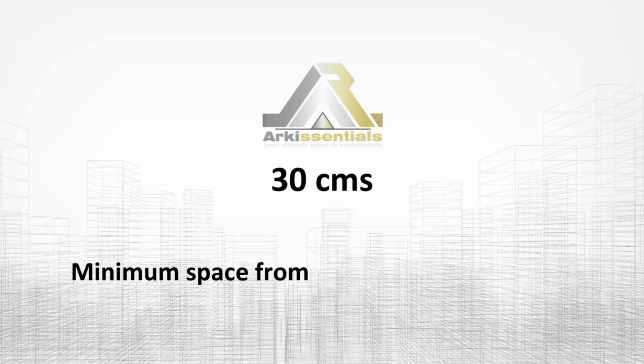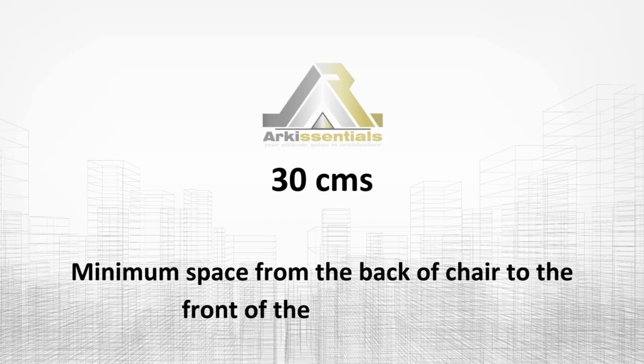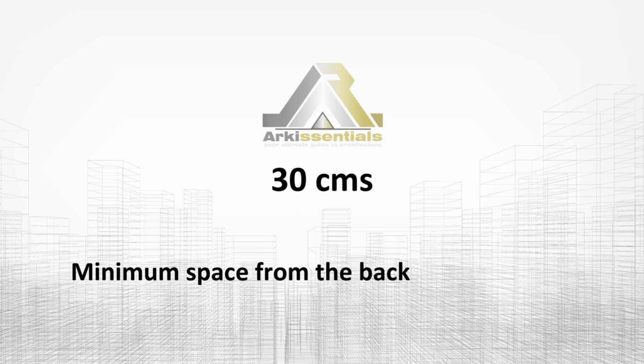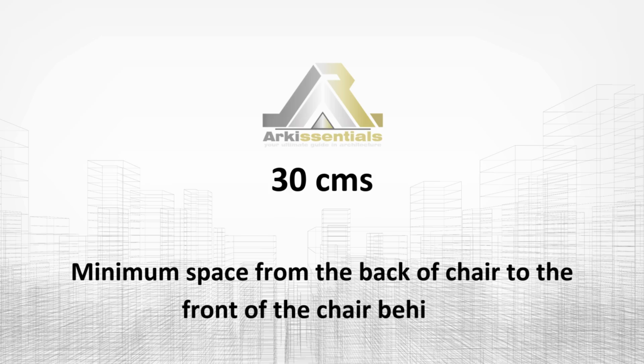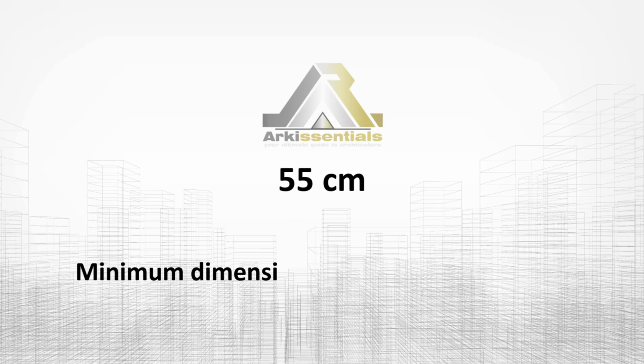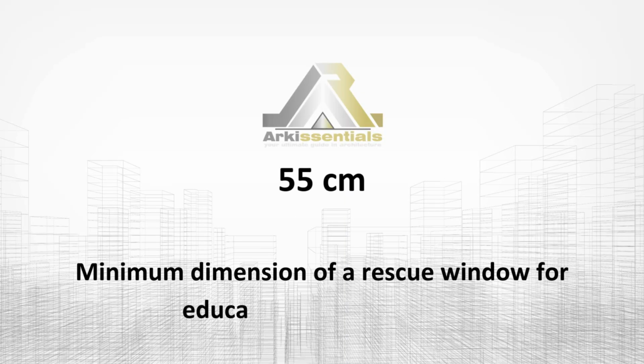Minimum space from the back of chair to the front of the chair behind is 30 centimeters. Minimum dimension of a rescue window for educational occupancies is 55 centimeters.